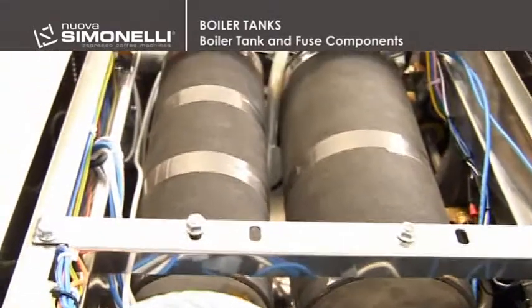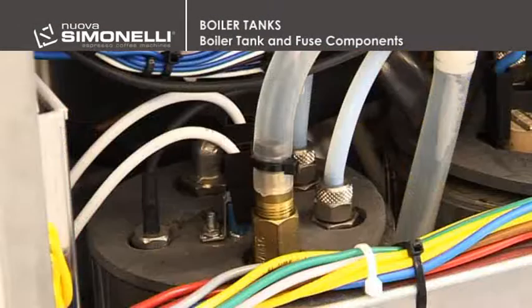Boiler tank and fuse components. The coffee boiler tank is comprised of a temperature probe, 16-bar expansion valve, hot water solenoid valve connection fitting, add water solenoid valve connection fitting, coffee solenoid valve connection fitting, safety thermostat, 98 degrees centigrade, CSA version for the North American market only.